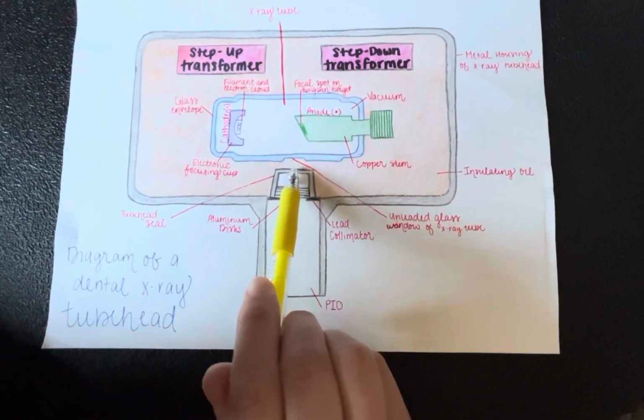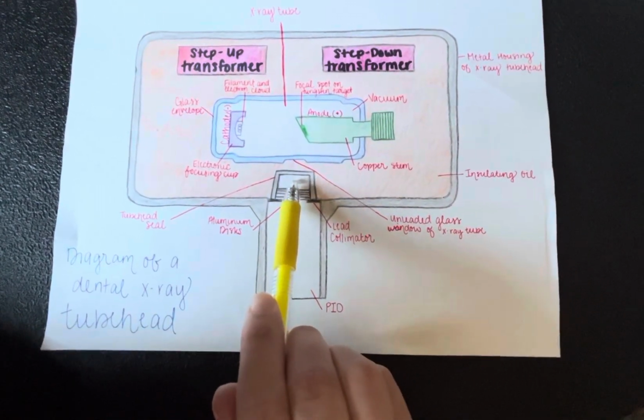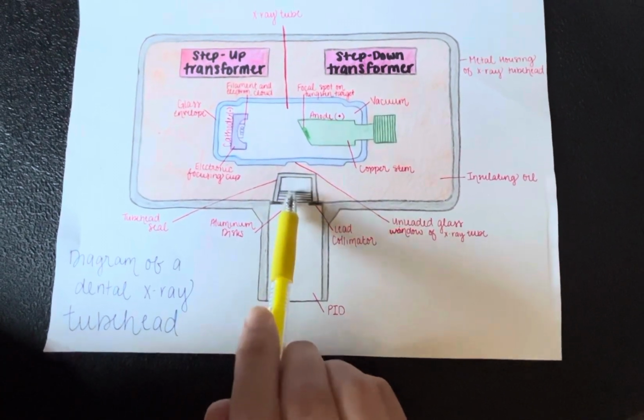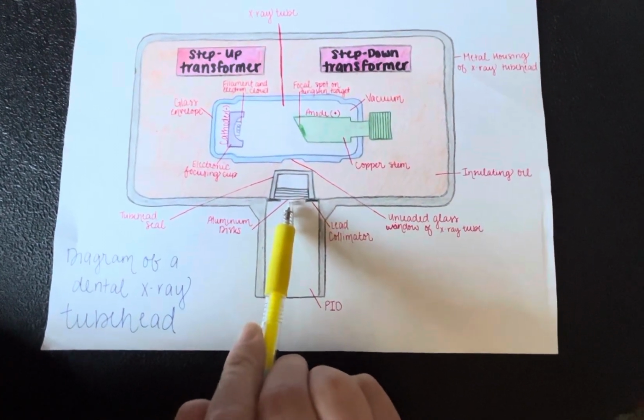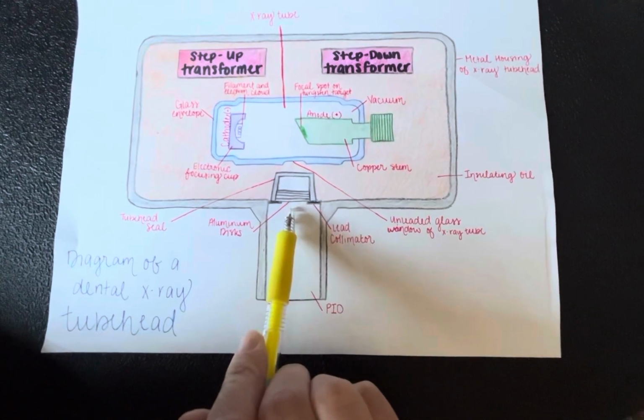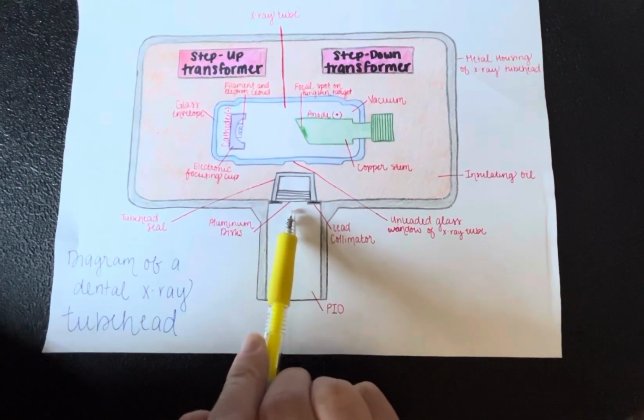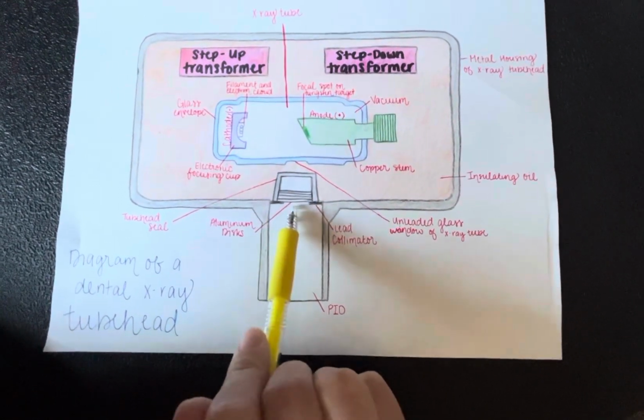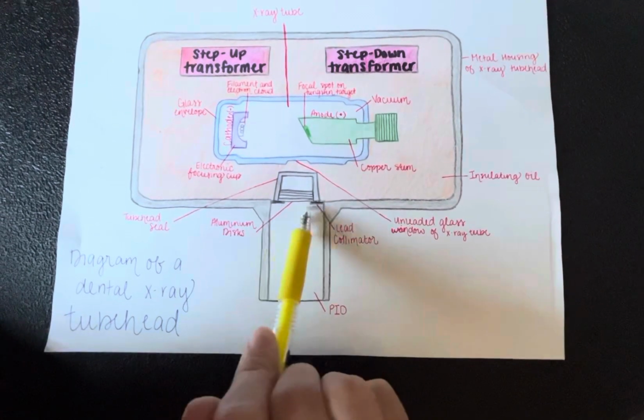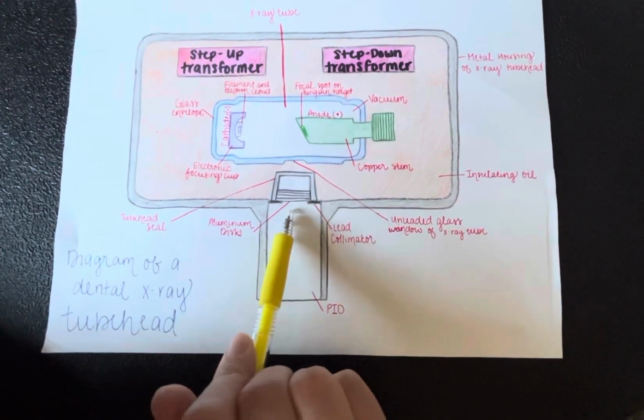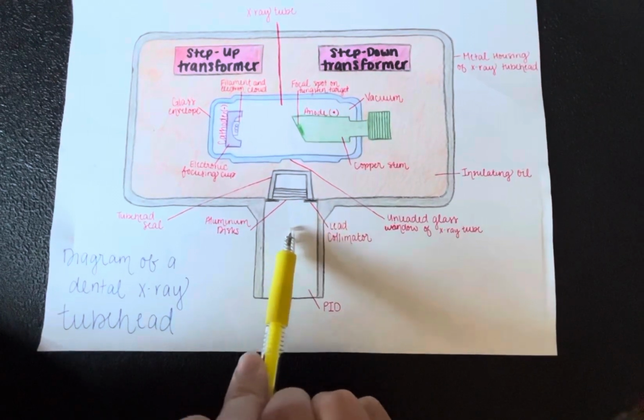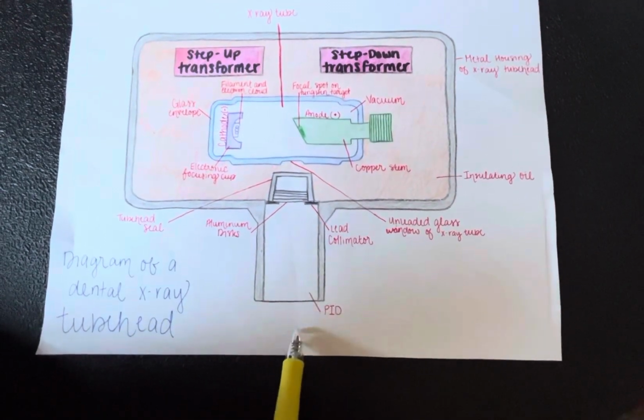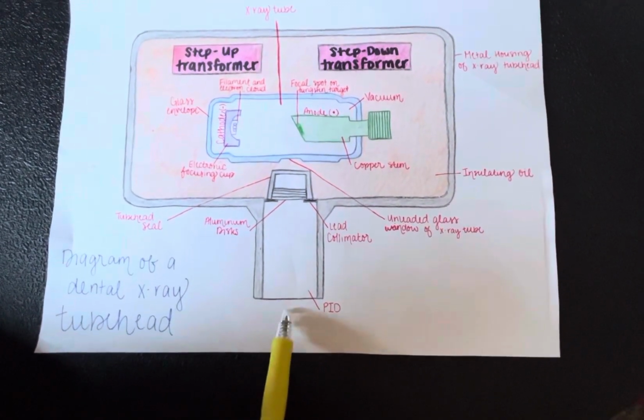The X-rays travel through the unleaded glass window, the tube head seal, and the aluminum discs, and the aluminum discs help filter out the longer low-energy X-rays. Finally, the lead collimator restricts the size and shape of the X-ray beam, and the X-rays travel down the PID and exit the tube head through the opening.